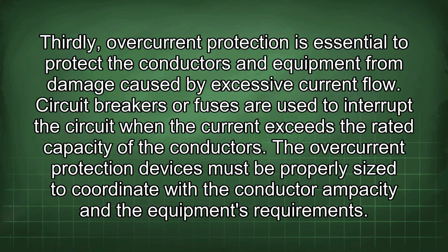Thirdly, overcurrent protection is essential to protect the conductors and equipment from damage caused by excessive current flow. Circuit breakers or fuses are used to interrupt the circuit when the current exceeds the rated capacity of the conductors. The overcurrent protection devices must be properly sized to coordinate with the conductor ampacity and the equipment's requirements.